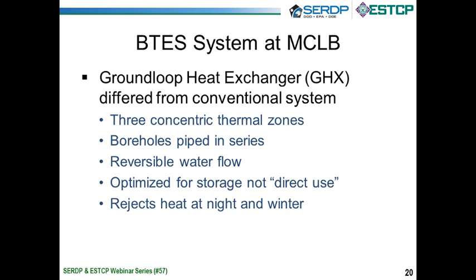But BTES systems differ from the way pretty much every other closed-loop system in the U.S. has been done so far, in that the boreholes are arranged in concentric thermal zones. So as you'll see shortly, looking a bit like an archery target, we have an inner zone, an intermediate zone, and an outer zone. So these three concentric thermal zones give us the ability to do some things we can't do with typical boreholes on a typical U.S. system that are piped in parallel, and you can't differentiate between an inner or a middle or an exterior borehole.